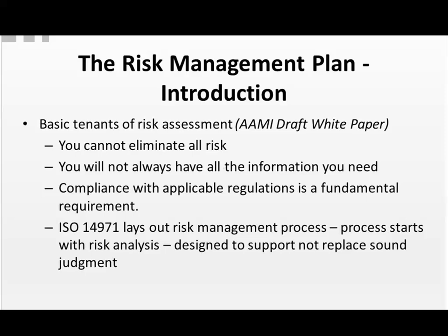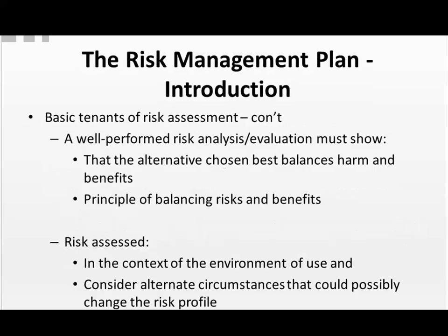Compliance with applicable regulations really is a fundamental requirement, as with everything that we do in life sciences. Risk principles really don't govern all the regulatory decision making. Now, ISO 14971-2007 lays out the risk management process for the U.S. and is recognized, as I said, by the FDA as a standard. Now, a well-performed risk analysis or evaluation really must show that the alternative chosen, when evaluating mitigating options, best balances harm and benefits based upon what was known at the time that the decision was made.